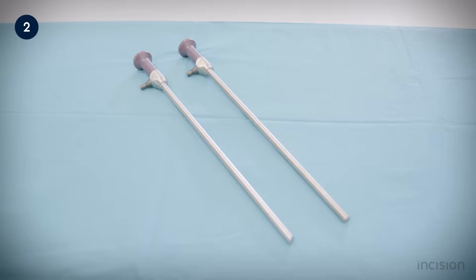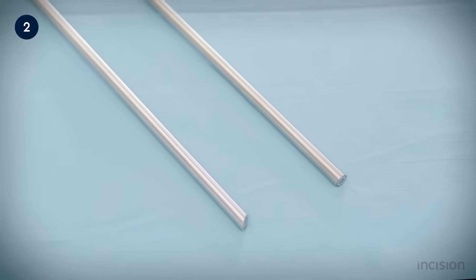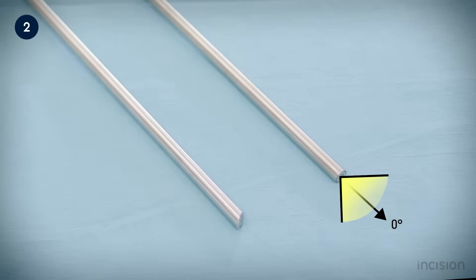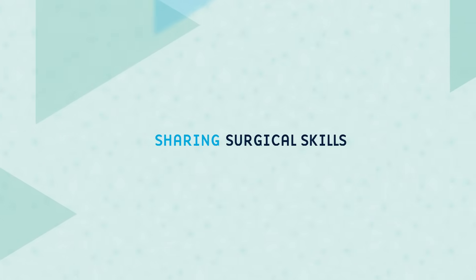Laparoscopes have different diameters, the most commonly used being 10mm, and the distal lens, or objective lens, can have different angles, changing the optical axis and allowing for different types of view, such as the zero-degree scope on the right of the screen, offering a straight-on panoramic view, and the 30-degree scope on the left, offering an oblique forward-facing view.